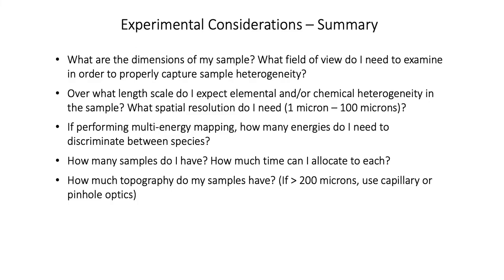In summary, key experimental considerations before coming to the beamline include: the dimensions of your sample; what field of view you need to capture sample heterogeneity; the length scale of elemental or chemical heterogeneity — i.e., what spatial resolution you need (1 micron vs. 100 microns); if performing multi-energy mapping, how many energies are needed to discriminate between species; how many samples you have and how much time to allocate to each; and finally, how much topography your samples have. If samples have greater than 200 microns of topography, you should consider capillary or pinhole optics at beamlines 7-2 and 6-2. All of this information is summarized on our beamline webpage at ssrl.slac.stanford.edu.